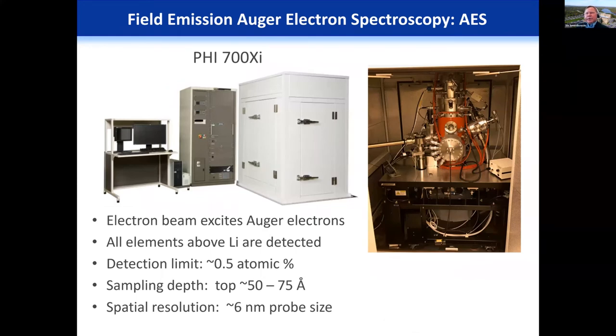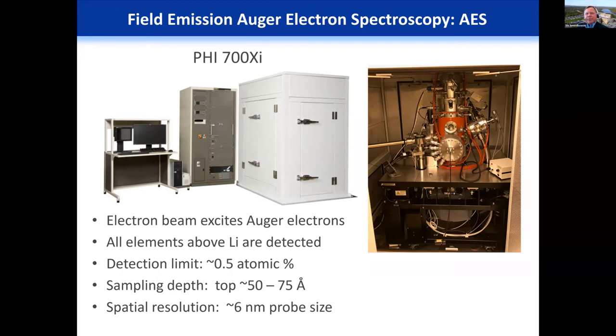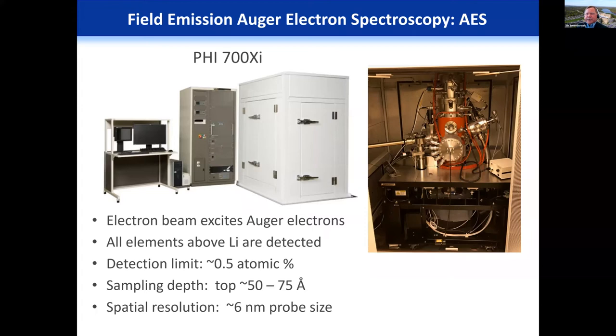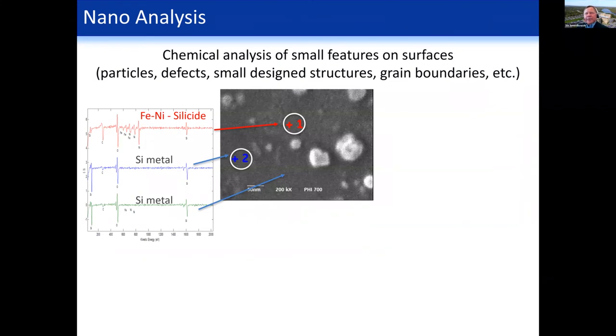Starting with Auger Electron Spectroscopy, referred to as AES. We have a PHI 700Xi instrument. By Auger, an electron beam excites Auger electrons; all elements heavier than lithium are detected; detection limits are about half an atomic percent; the sampling depth is about 50–75 angstroms; and for our instrument the spatial resolution can be defined by a probe size of about 6 nanometers.